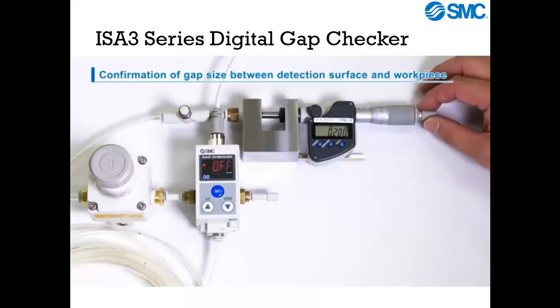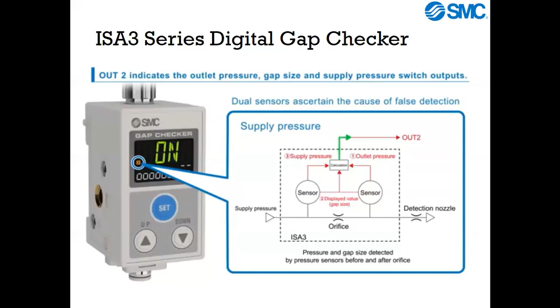The ISA3 includes features like two sensors to detect supply and outlet pressure, helping determine whether there is a clog or not. There is the supply pressure detection sensor and the detection nozzle pressure, the back pressure coming from the detection nozzle. A calculation is done, and finally there is an output which gives an indication of whether the correct seating has been achieved and the correct gap is being maintained. That is, in brief, about the ISA3 series gap checker.